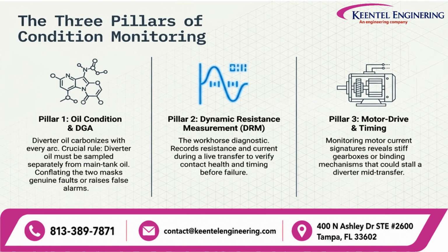The second pillar is dynamic resistance measurement, or DRM. DRM evaluates contact condition during tap changer operation and identifies worn or damaged switching contacts. The third pillar is motor drive monitoring, which analyzes operating time, torque, current, and mechanical performance. Combining these three diagnostic techniques allows utilities to detect developing problems long before they become costly failures.